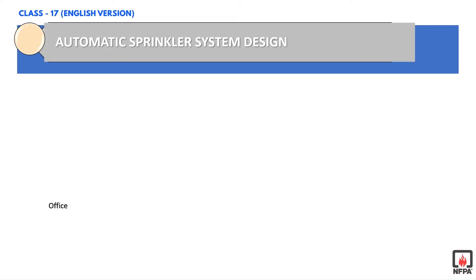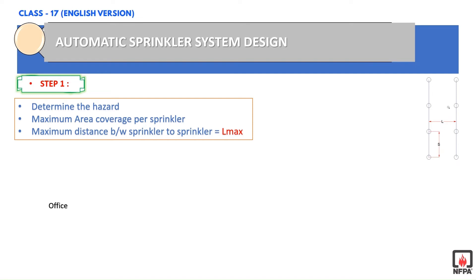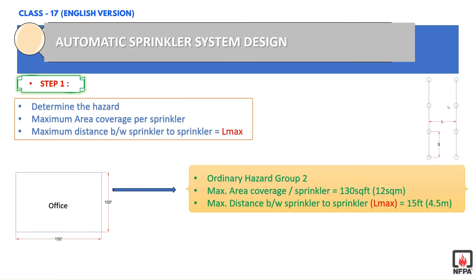Step 1: Based on the building application — in this example, an office — the occupancy hazard classification must be identified along with the maximum area covered by one sprinkler and the maximum distance between sprinklers. Our office has stockpiles of 10 feet, which classifies it as ordinary hazard group 2. The maximum area covered per sprinkler is 130 square feet as per NFPA 13, and the maximum distance between sprinklers is 15 feet (approximately 4.5 meters) per NFPA 13 requirements.